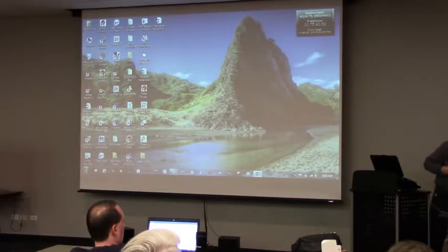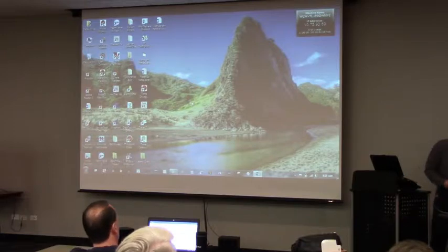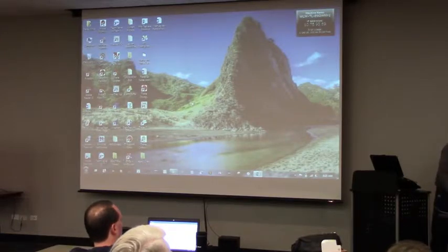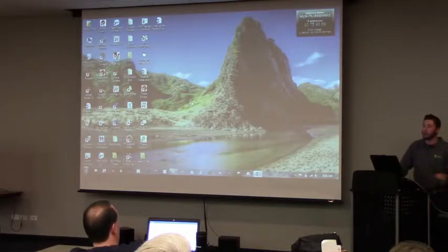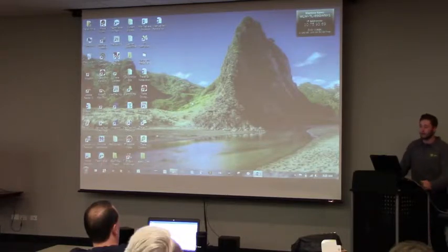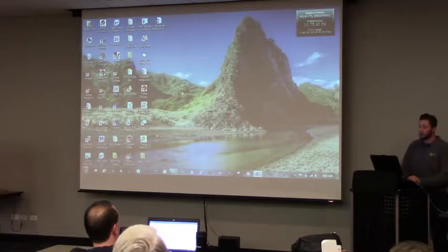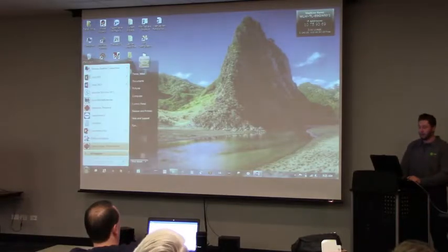And then just for you guys, I only have a BCU here, but it's the same thing. They have a mini monitor port right down here. You can stick this right into there. And one of the biggest things, just so you guys know, is it has to be COM1 or COM2 for your port to connect to a BCU or PCM or UPCM. And on top of that, you have to change your flow control to Xon and Xoff for your connection. So I'm going to go under Device Manager and just make sure that all that stuff is set up properly.